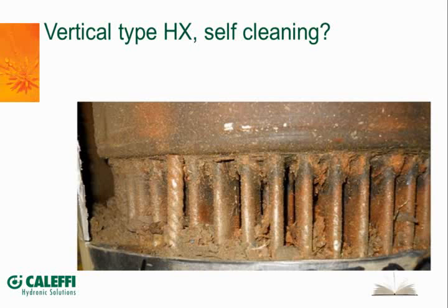And here's one that you provided. Yeah, and one of the selling features of this type of boiler was that it had a self-cleaning heat exchanger. It was a tube type of boiler instead of that little serpentine coil, and they say, oh, yeah, they're self-cleaning, they won't plug up. But again, garbage in, garbage out. It's like the early days of computers. Whatever you put into them is what they spit back out. If you put in bad water quality, you keep adding fresh water or hard water or rusty water into a heat exchanger, it doesn't matter that it's a self-cleaning design. It still has the potential to plug up, and of course this is going to overheat and fatigue the metal, just like the other type of heat exchanger on the different style boiler.